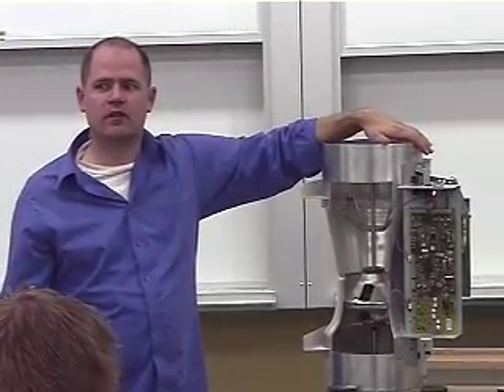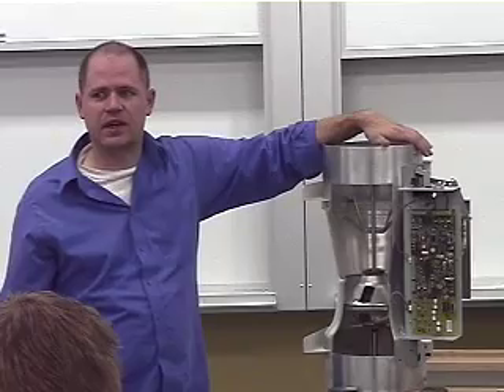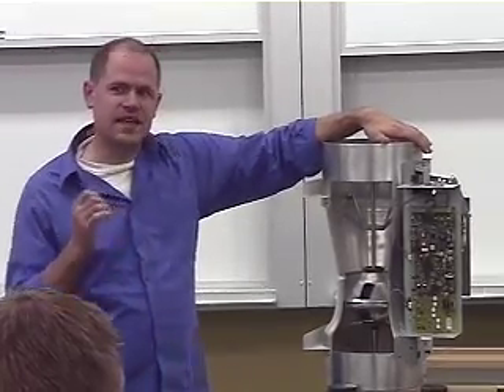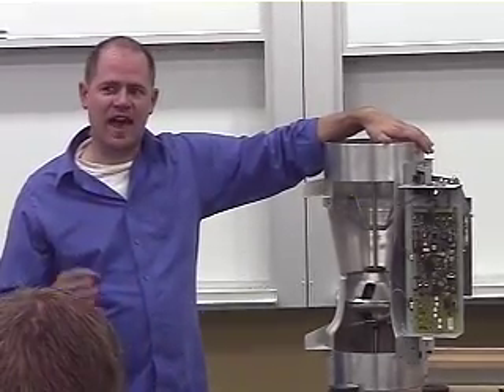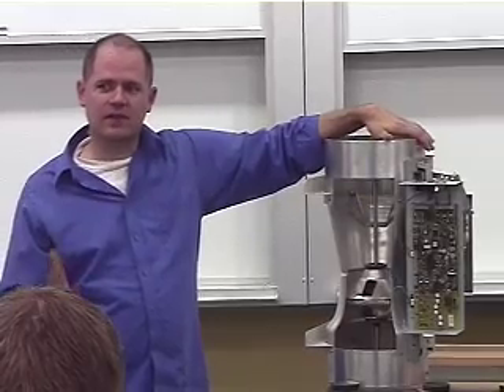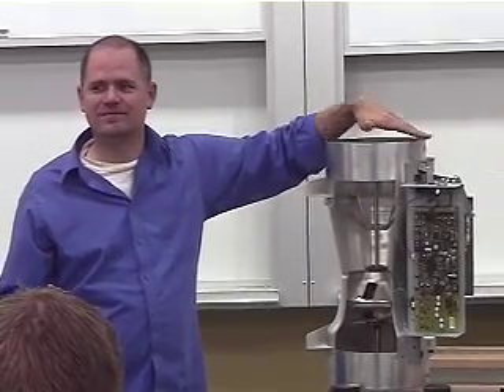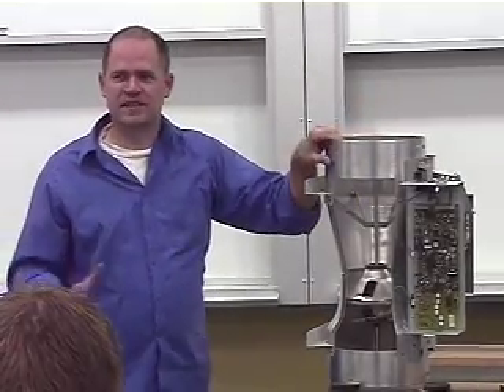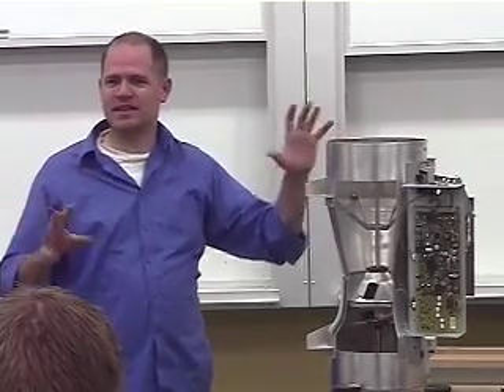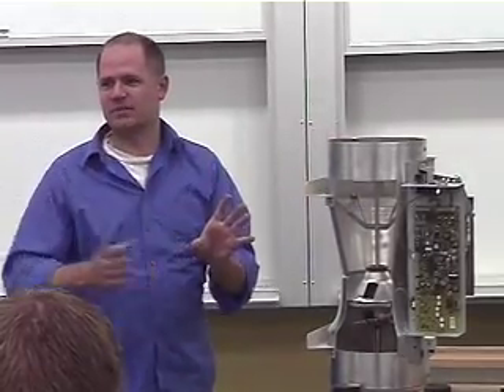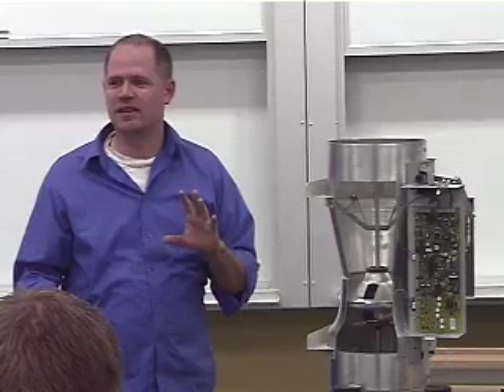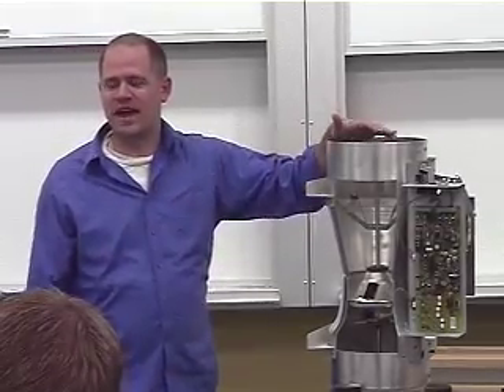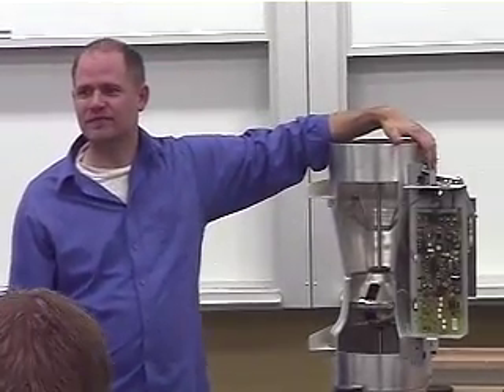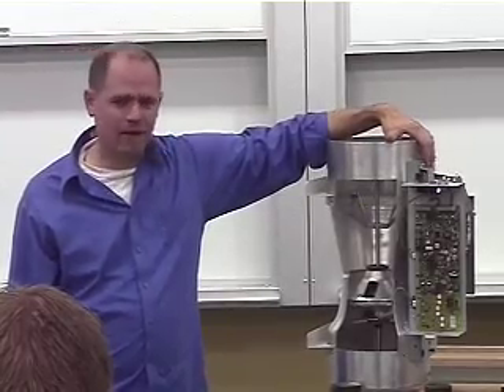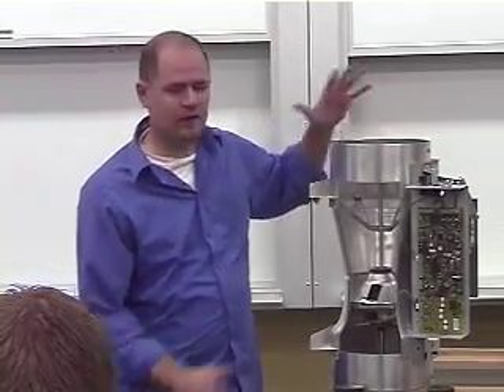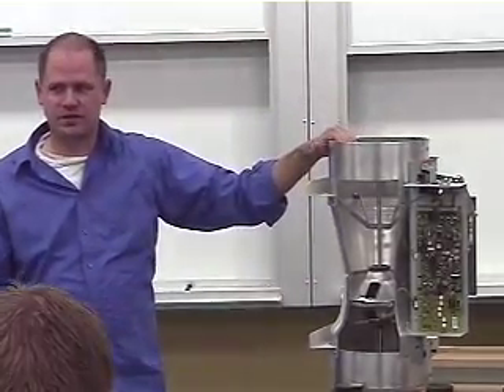That's a custom flow curve calibrated at the factory to indicate exactly what flow it will have at that position if the pressure requirements are met. So does that make sense as far as those three things have to be the case? It has to be in the right position, pressure has to be across it, and it has to be able to move it to get there. That's the basics of what a Phoenix valve is and how it works.